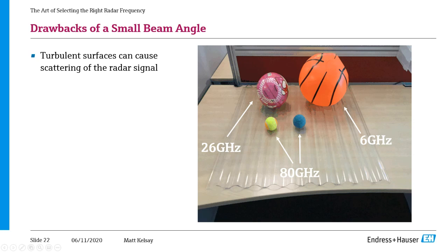However, there is a little bit of a drawback, and the main one is turbulent surfaces. So on the picture here, we'll pretend that this little plastic wavy piece is a product surface. So maybe you've got a small mixing agitator in a tank, or maybe you're filling from above. It's creating some turbulence on the surface. We focus on first the basketball. That would be representative of a low frequency unit. So a big beam angle is going to give you a big footprint on the product surface. The benefit here is that big footprint.